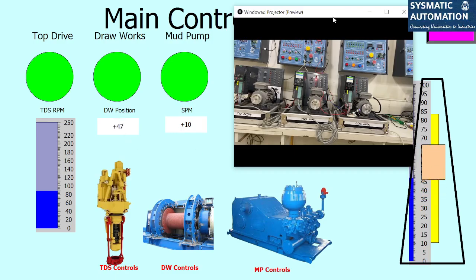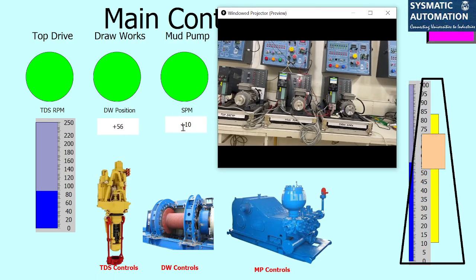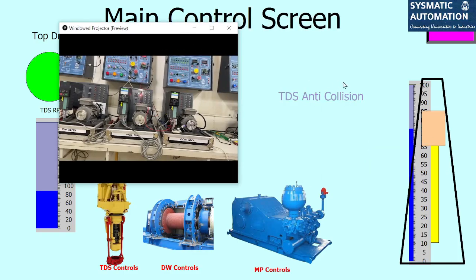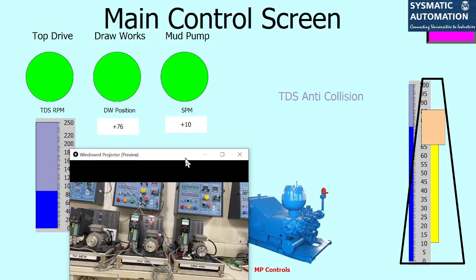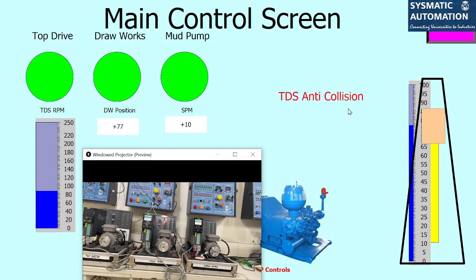Note that the moment it reaches around 70 position, it will slow down. See, the moment it reaches 70 feet height, the drawworks automatically slows down because it is in the anti-collision region now. Right? It will stop at the position where the maximum height is set. All these settings are done in my PLC program.